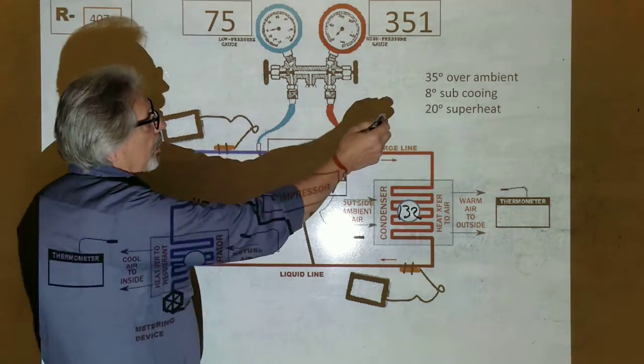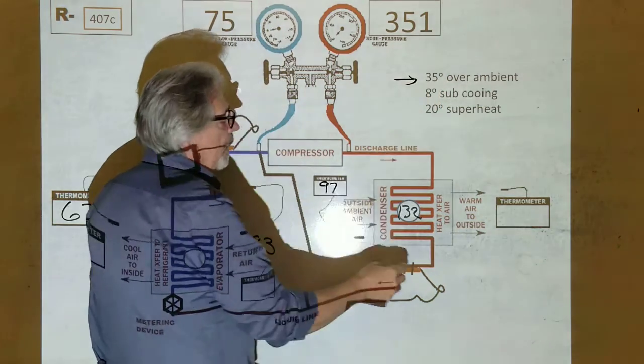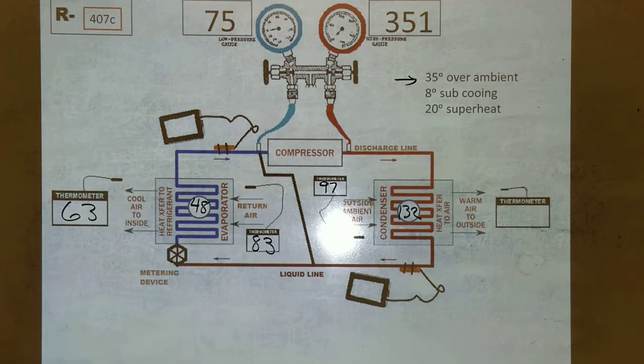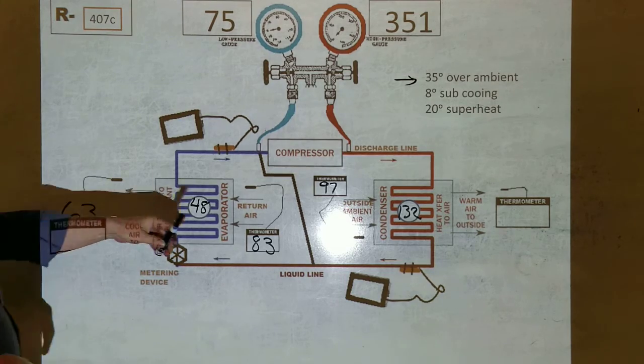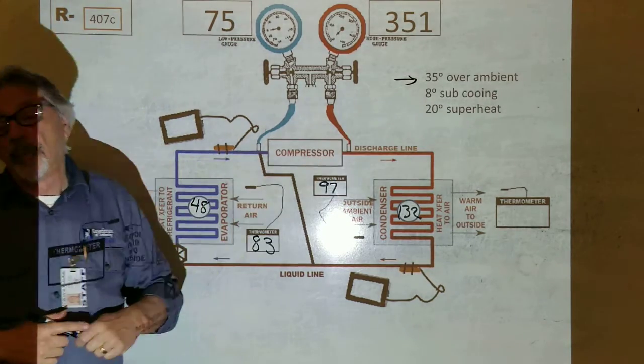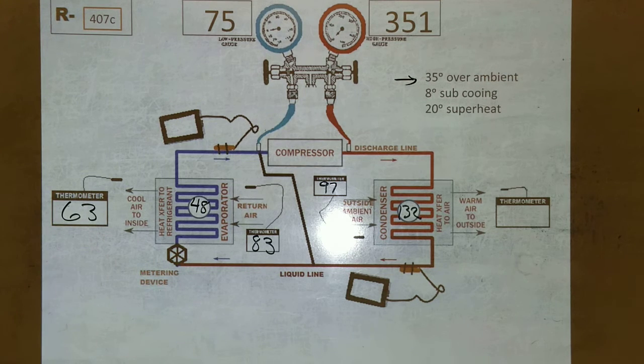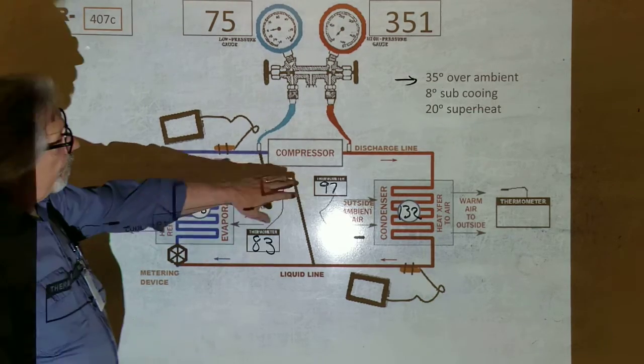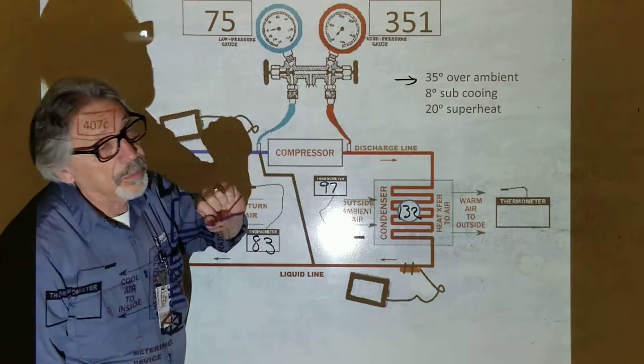This is gonna vary quite a bit. This is a condenser temperature, and the approach on the condenser side is gonna vary depending on the year and the efficiency of that unit. It could be anywhere from 20 degrees to 35 degrees. There's no way of knowing exactly what it's supposed to be because of the energy efficiency. Some units are more efficient than others, so they're gonna have better subcooling, and the condensers are a little bit bigger, so that throws off this delta T here. So we don't go by that anymore.